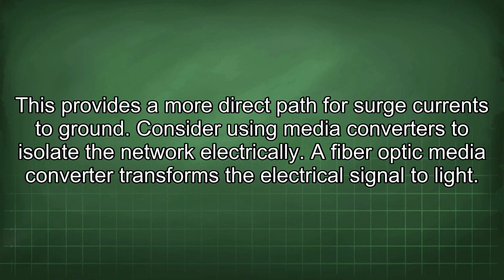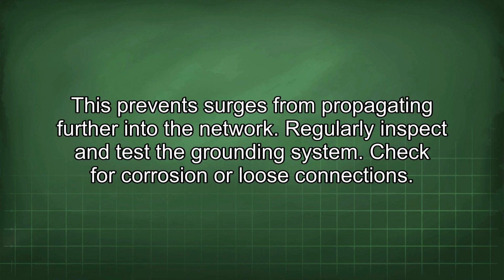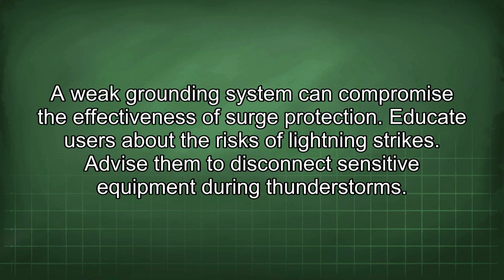Consider using media converters to isolate the network electrically. A fiber optic media converter transforms the electrical signal to light. This prevents surges from propagating further into the network. Regularly inspect and test the grounding system. Check for corrosion or loose connections. A weak grounding system can compromise the effectiveness of surge protection.